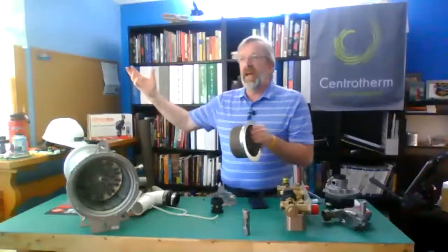Now, once I'm lit, and we're talking specific to residential today, at low fire, this merely glows. So for those of you that go out and sit on the porch, or used to go to the restaurant, we don't get to anymore, they've got those outdoor heaters, that's what we're looking for. It should look like that infrared heater, that orange glow. As I ramp up, I'm going to turn a little bluish purple, but I'm still going to have those orange speckles underneath. Whatever my flame pattern, whatever it looks like, I want it consistent all the way around.